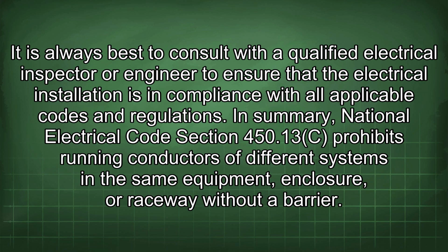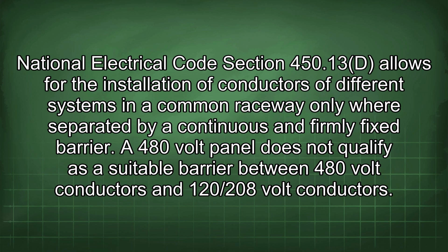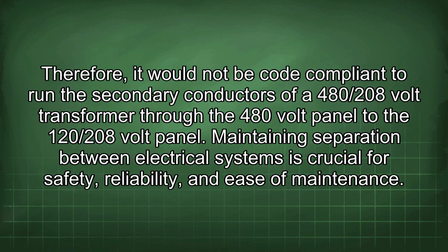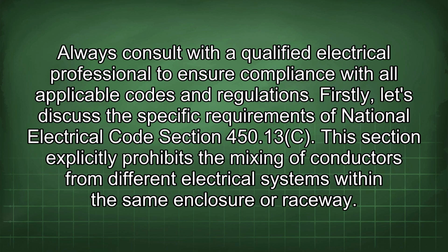In summary, National Electrical Code Section 450.13c prohibits running conductors of different systems in the same equipment, enclosure, or raceway without a barrier. National Electrical Code Section 450.13d allows for the installation of conductors of different systems in a common raceway only where separated by a continuous and firmly fixed barrier. The 480 volt panel does not qualify as a suitable barrier between 480 volt conductors and 120/208 volt conductors. Therefore, it would not be code compliant to run the secondary conductors of a 480/208 volt transformer through the 480 volt panel to the 120/208 volt panel. Maintaining separation between electrical systems is crucial for safety, reliability, and ease of maintenance. Always consult with a qualified electrical professional to ensure compliance with all applicable codes and regulations.